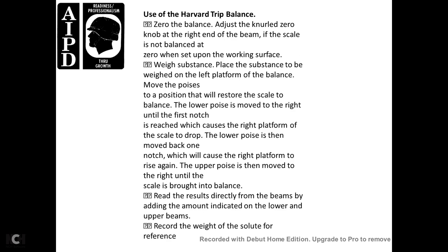Using the Harvard Trip Balance: zero the balance by adjusting the zero knob at the right end of the beam. If the scale is not balanced at zero when set up, place the substance to be weighed on the left platform. Move the poise to the position that restores the scale to balance. The lower poise is moved to the right until the first notch is reached causing the right platform to drop; move it back one notch which will cause the right platform to rise. Move the upper poise to the right until balance is achieved. Read the result directly from the beams by adding the amounts indicated on the lower and upper beams. Record the weight for reference.